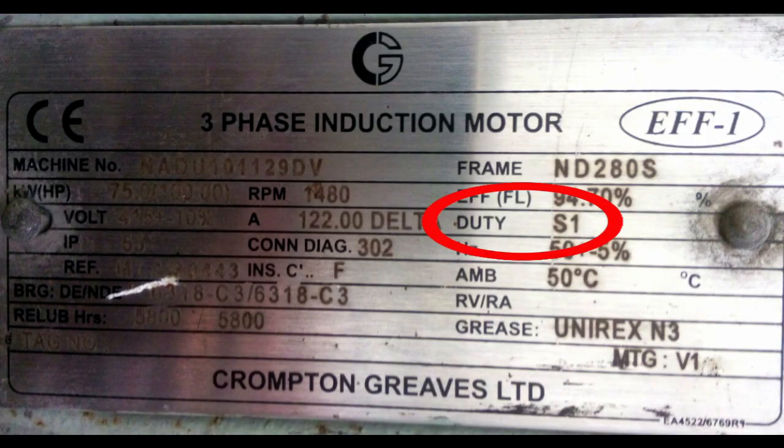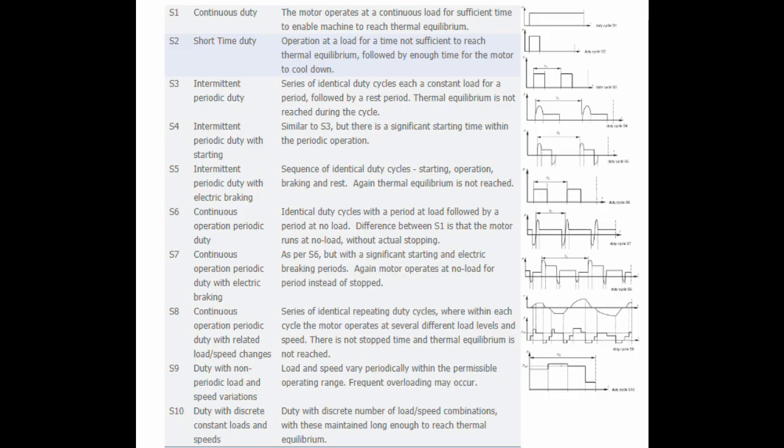Next is the duty cycle. Duty means the load cycle to which the machine is subjected and it may include starting, electric braking, no load, and rest de-energized period. The term cycle duration factor is the ratio between the period of loading to the duration of the duty cycle in percentage. We can define duties into 10 types from S1 to S10.